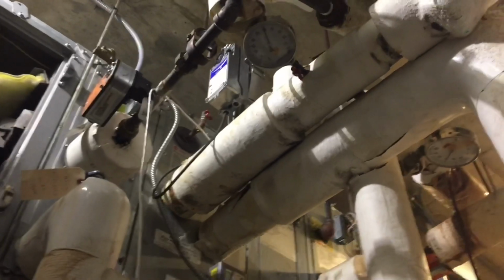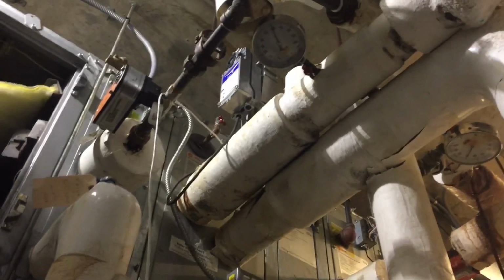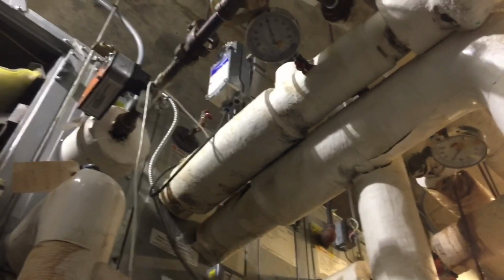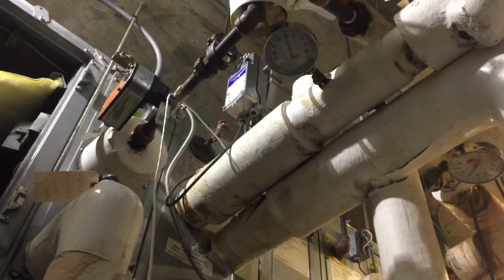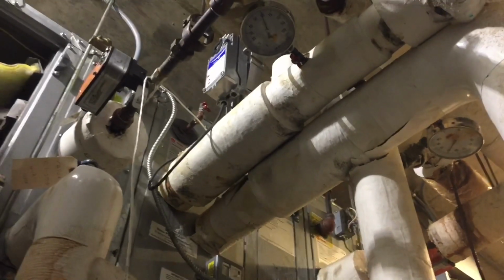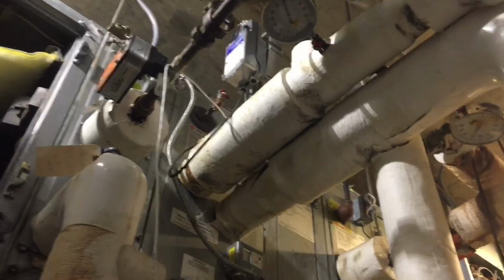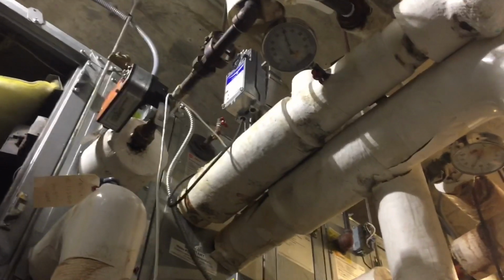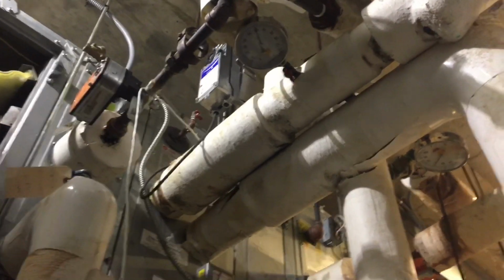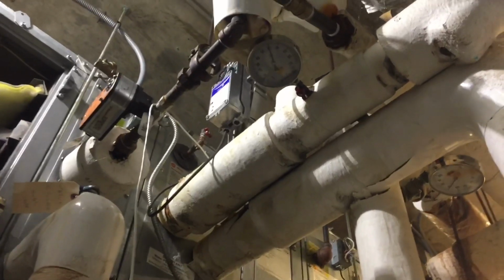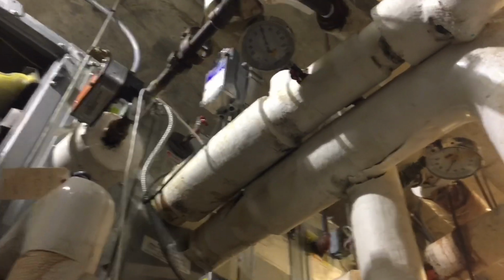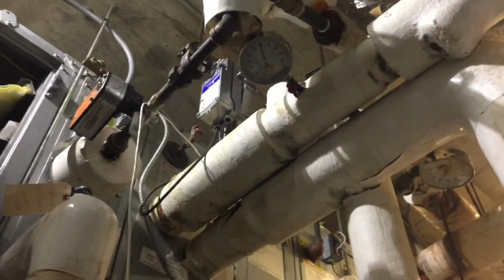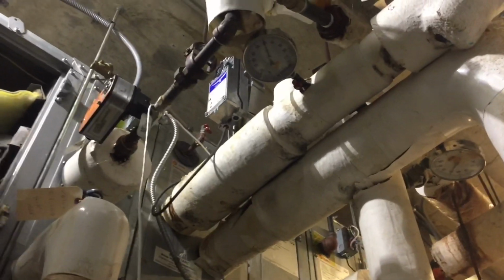So they tried every wire combination, it didn't work. So I came here, I did the same thing, I troubleshot it, checked power, checked signal, I had all of that, everything was good, but it wasn't connected to the actuator. When it was connected to the actuator, I would get a weird voltage reading on this DC 0 to 10 signal, at like 20 volts DC. So it was kind of strange.